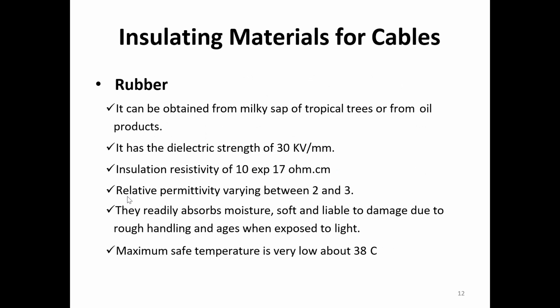The common material used for insulation is rubber. What are the properties of rubber? It has dielectric strength of 30 kV per mm, and insulation resistivity of 10 raised to power 17 ohm centimeter. Relative permittivity is between 2 to 3. We need to see the maximum safe temperature because temperature effect matters a lot, since in underground cable as current flows, heat is produced, and in underground installations we place cables in situations where temperature is very high, so we must check thermal stability of the cable, and this will be used up to 38 degrees C.